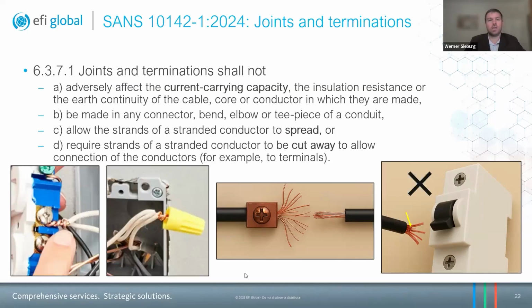In other words, if I chase a high current through a cable that is continuous and I chase the same current through a cable that contains a joint, the resistance or the heating patterns of the continuous cable and the one where a joint is included must not materially differ. And so it's an outcome-based requirement. Right, number B, it must not be made in any connector, bend, or elbow, or T-piece of a conduit.